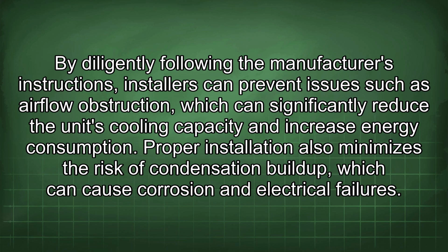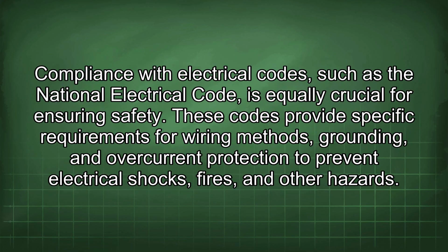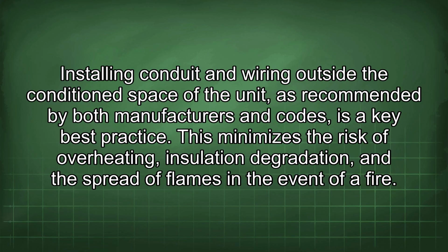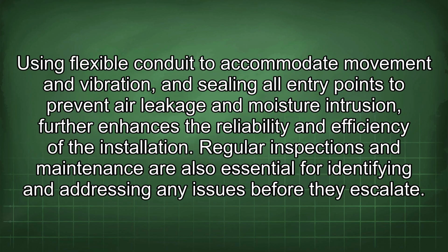Proper installation also minimizes the risk of condensation buildup, which can cause corrosion and electrical failures. Compliance with electrical codes, such as the National Electrical Code, is equally crucial for ensuring safety. These codes provide specific requirements for wiring methods, grounding, and overcurrent protection to prevent electrical shocks, fires, and other hazards. Installing conduit and wiring outside the conditioned space of the unit, as recommended by both manufacturers and code, is a key best practice. This minimizes the risk of overheating, insulation degradation, and the spread of flames in the event of a fire. Using flexible conduit to accommodate movement and vibration, and sealing all entry points to prevent air leakage and moisture intrusion, further enhances the reliability and efficiency of the installation.